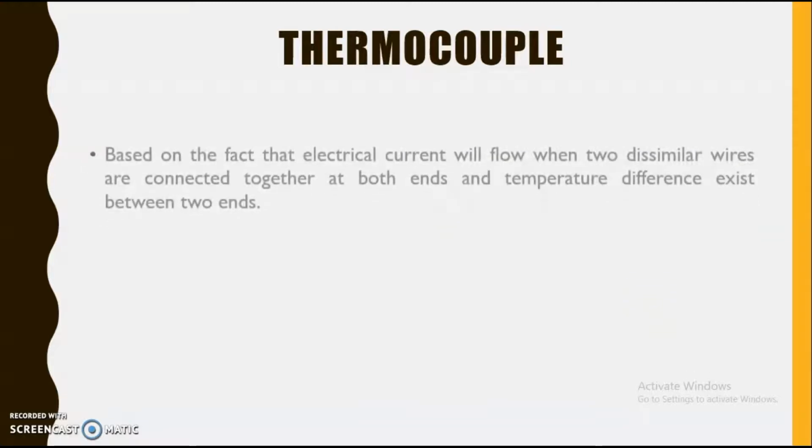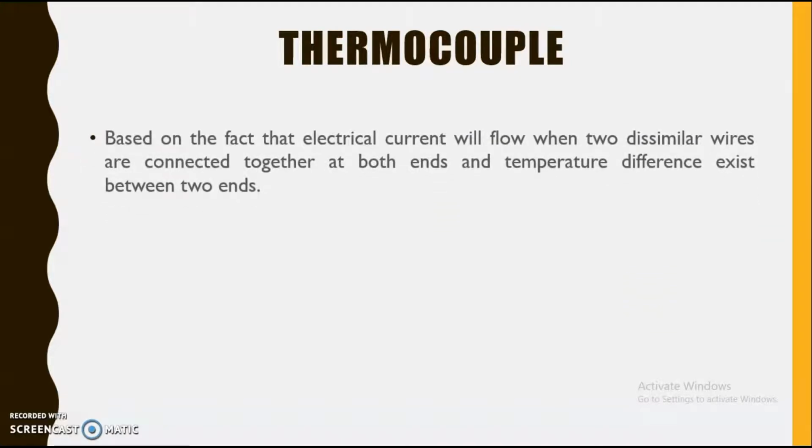Then the second most commonly used detector is the thermocouple. This thermocouple is based upon the fact that electric current will flow when two dissimilar wires are connected together at both the ends, and a temperature difference exists between the two ends.